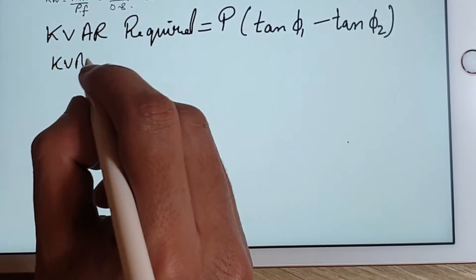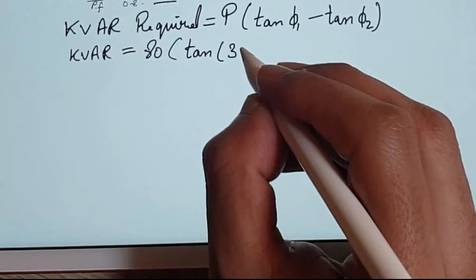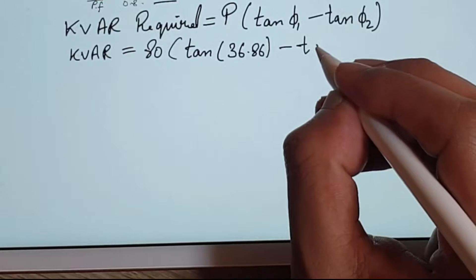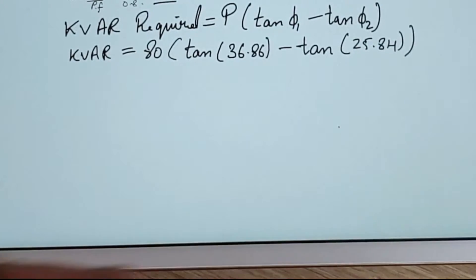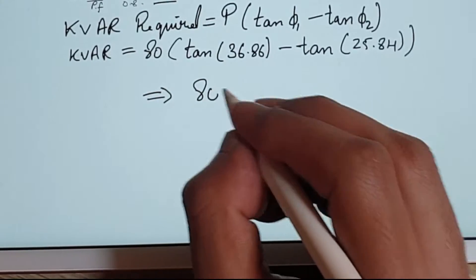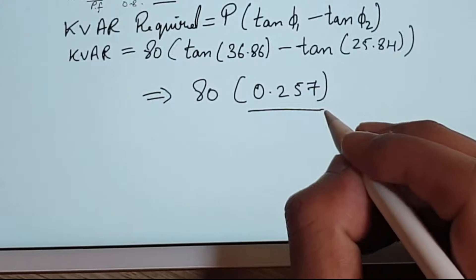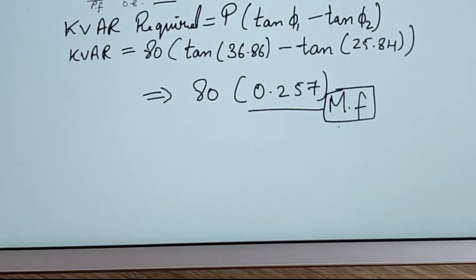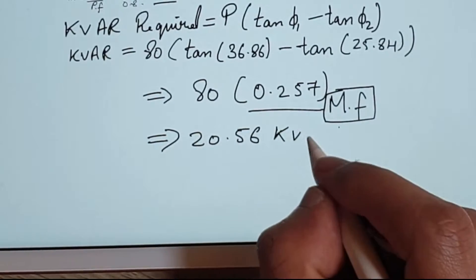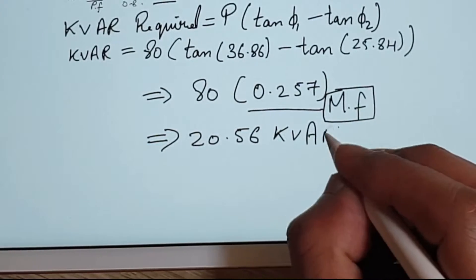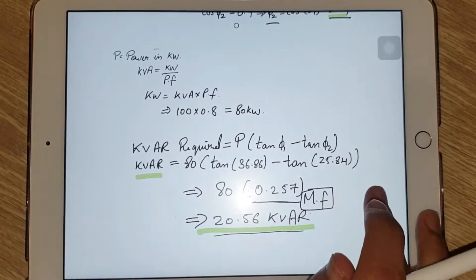Substituting into the required KVAR formula: P × (tan θ1 − tan θ2) = 80 × (tan 36.86° − tan 25.84°). This gives 80 × 0.257, where 0.257 is the multiplying factor (tan θ1 − tan θ2). So 80 × 0.257 = 20.56 KVAR, which is the required KVAR for improving the power factor from 0.8 to 0.9.